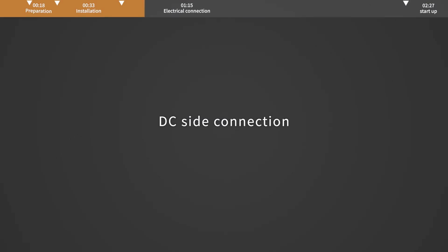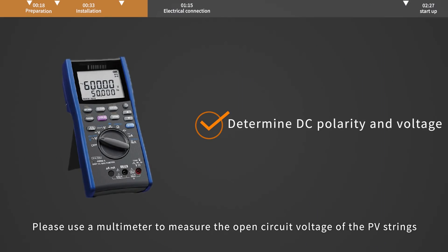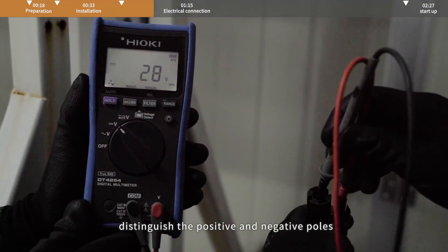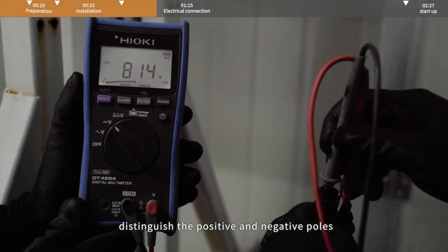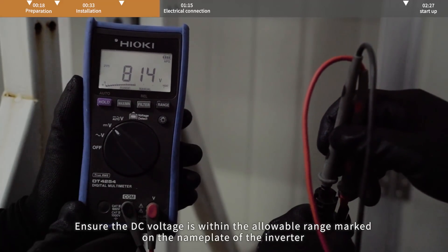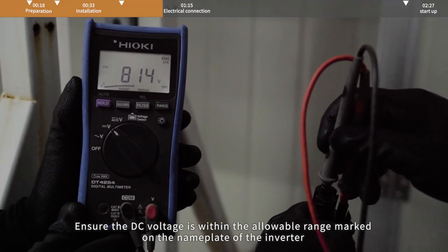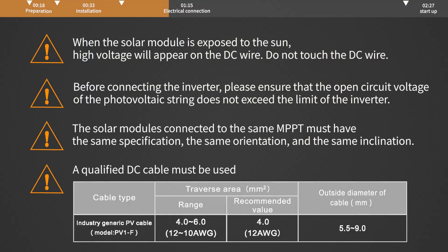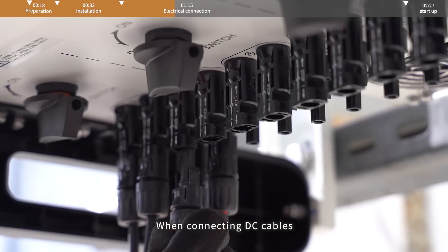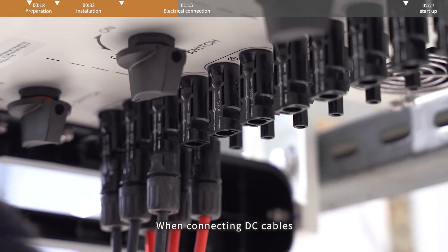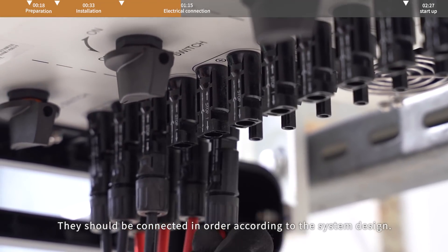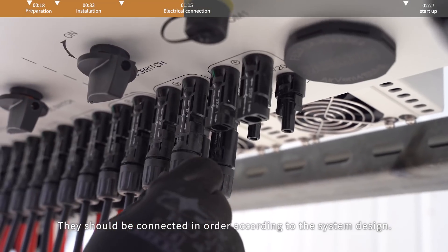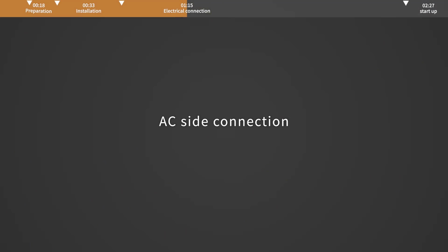DC side connection. Please use a multimeter to measure the open circuit voltage of the PV strings and distinguish the positive and negative poles. Ensure the DC voltage is within the allowable range marked on the nameplate of the inverter. When connecting DC cables, they should be connected in order according to the serial number marked on the body.